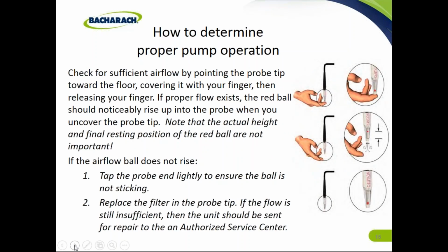How to determine proper pump operation? Check for sufficient airflow by pointing the probe tip towards the floor, covering it with your finger, then releasing your finger. If the proper flow exists, the red ball should noticeably rise up into the probe when you uncover the probe tip. Note that the actual height and the final resting position of the red ball are not important. If the airflow ball does not rise, tap the probe lightly to make sure the ball is not sticking. Replace the filter in the probe tip. If the flow is still insufficient, then the unit should be sent in for repair.